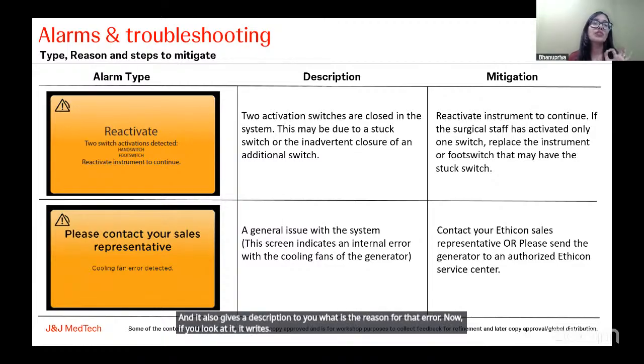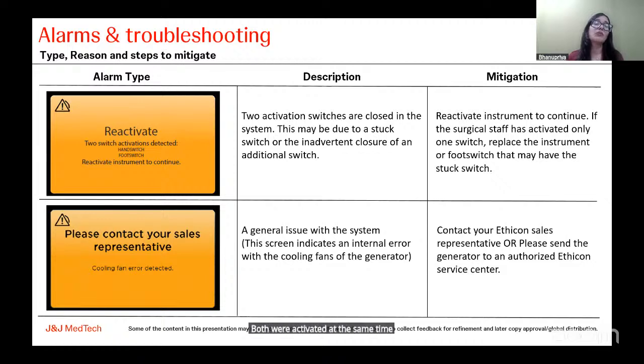So for example, if you look at the first error, it says reactivate, and it also gives you a description of the reason for that error. Now, if you look at it, it writes two switch activations detected. That means your hand switch as well as your foot switch were both activated at the same time. So you might have pressed the foot switch and the hand switch together. That could be the reason why the error has populated.